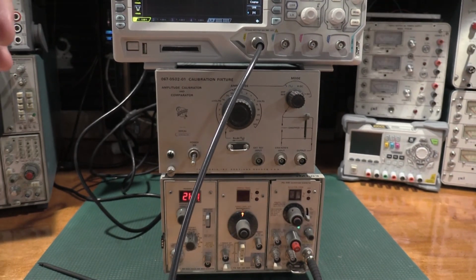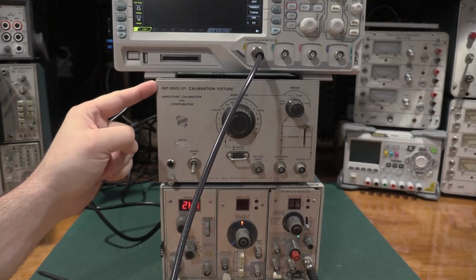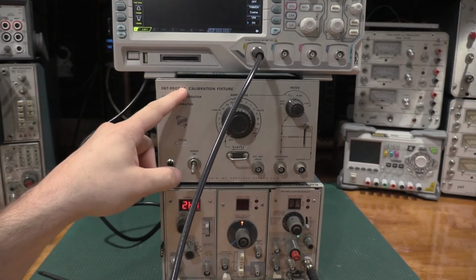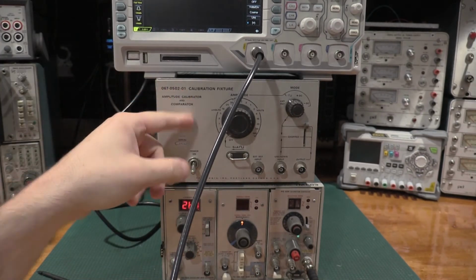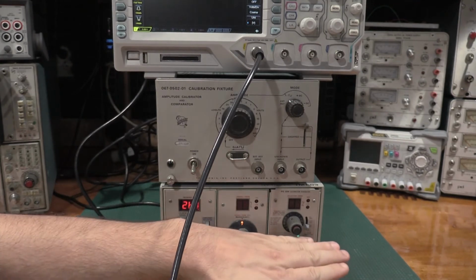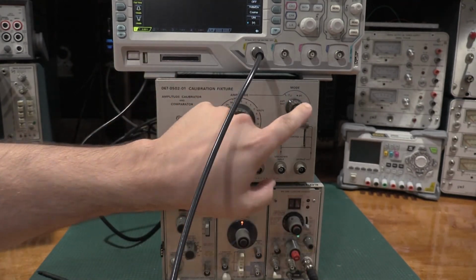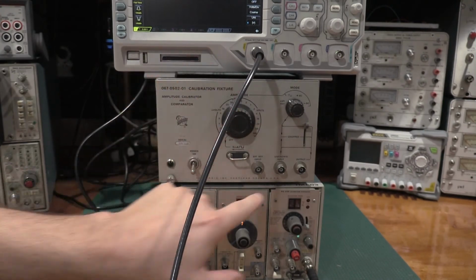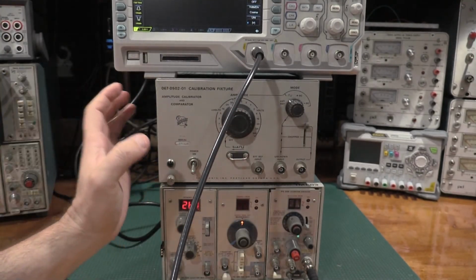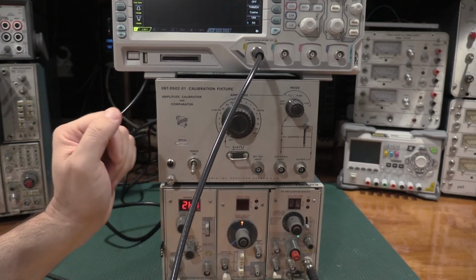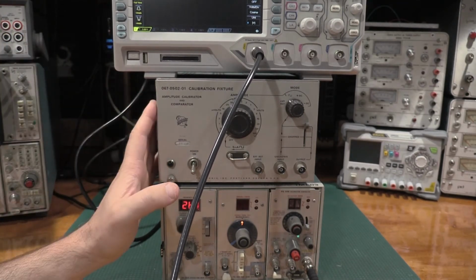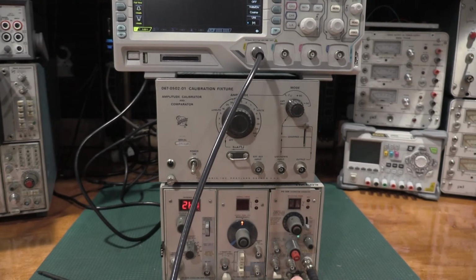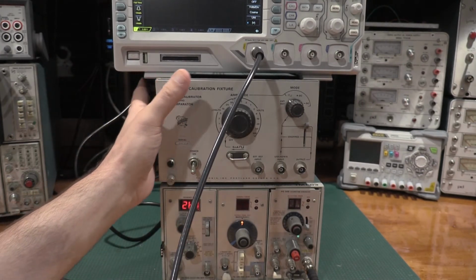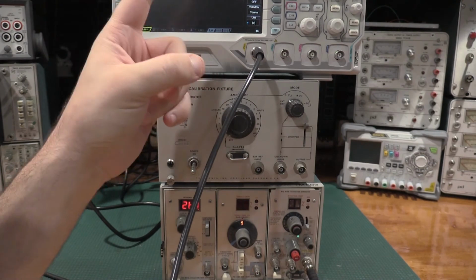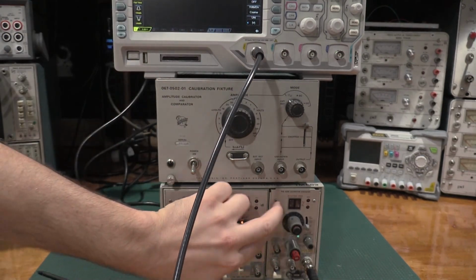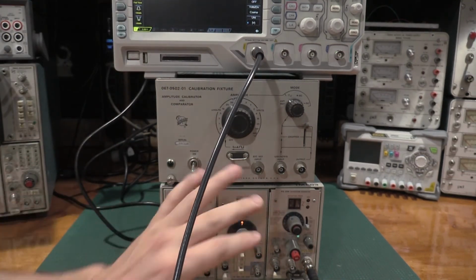The Leaning Tower of Test Gear. The 67502-1 or -0. This gives you the top half of a 506. The calibration generators with some other features, you can chop a voltage in and out, but this gives you the calibrated amplitudes to send out to the scope, so you can do the calibration. Also the 5 milliamp square wave, which is duplicated down here. So this unit plus a Type 106 combined make a PG506. That's what the two units do.